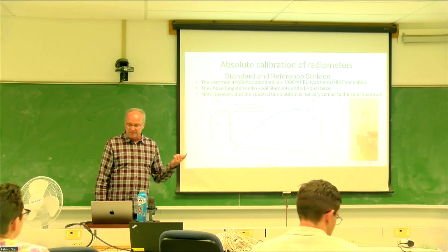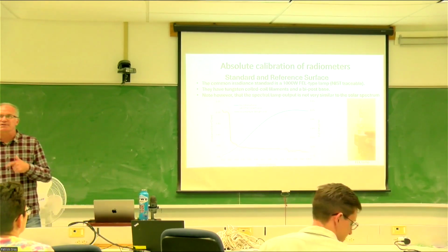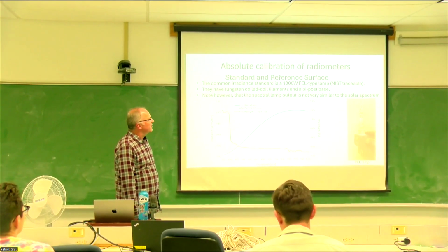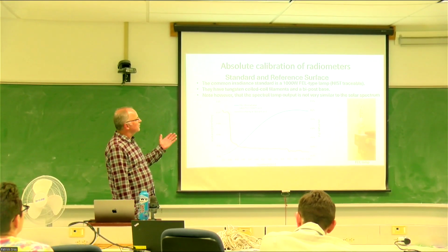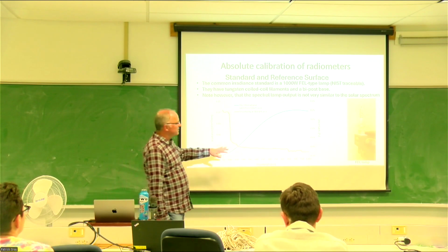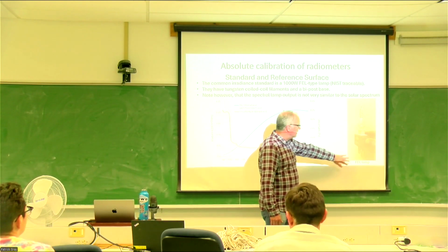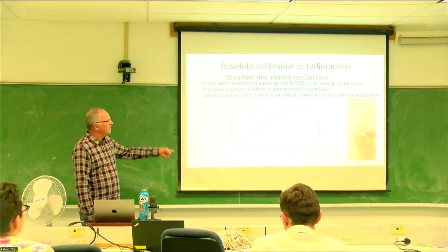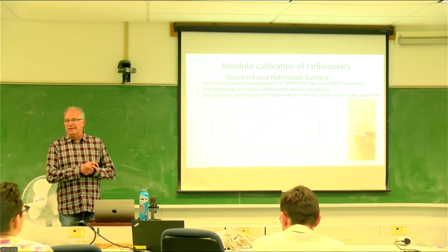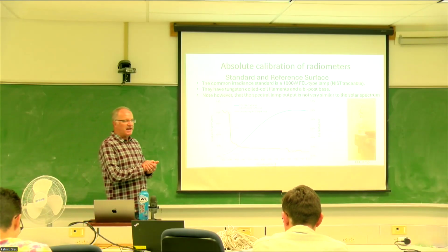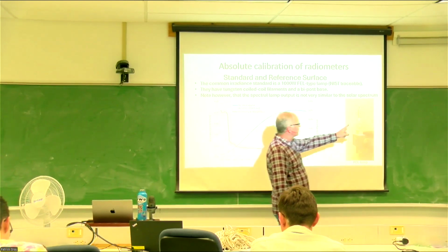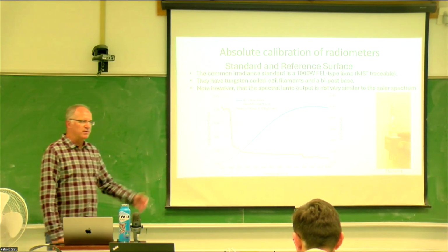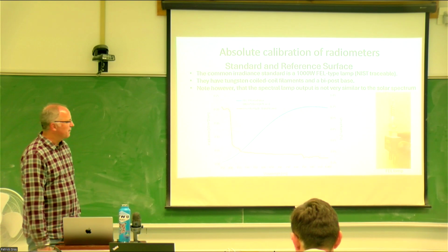So in terms of this, what I'm about to say is a generalization because it's not quite true, but the method for the absolute calibration of radiometers, the standard, which in this case for irradiance and radiance, is a very traceable light source called an FEL. It's a 1,000 watt output FEL lamp, and it also has to be exceedingly stable in its output. So here's a little tungsten coil comes up through it. Tungsten is a very bright emitter of light when you put in enough wattage to that lamp.